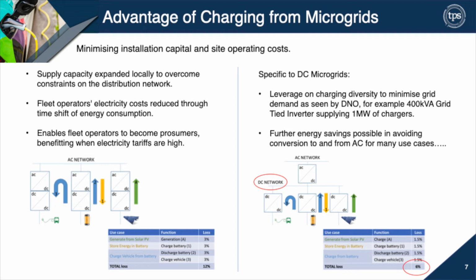So why particularly do we want to look at DC microgrids? Well, we can kid the DNO to some degree. If you want 1 megawatt of charger, we can connect all of those to the grid with a 400 kilowatt grid-tied inverter. As far as the DNO is concerned, that's 400 kilowatts of charging power, but I've got 1 megawatt of charger. So through natural diversity of charge state, and potentially a bit of addition of battery storage or solar PV, you are creating that capacity locally and potentially avoiding that big upgrade cost.